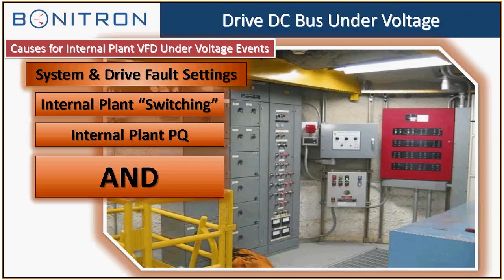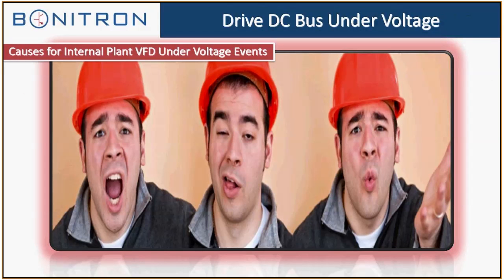So what we run into a lot of times is internal plant switching, load switching, and the internal plant power quality situation. Along with the utility power, you also have to be concerned with what kind of events are going on in the plants. Chances are you're going to be dealing with the maintenance guys, the internal plant electricians and engineers, and it's going to be part of your job to be able to explain to them issues with configuration, installation, meeting their specification, and any other requirements for ride-through that they're going to have to deal with.